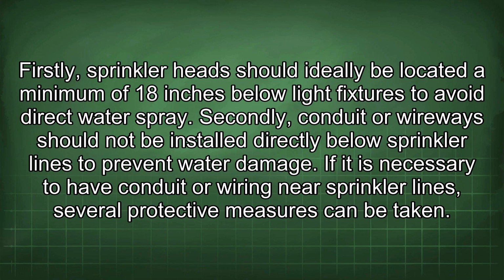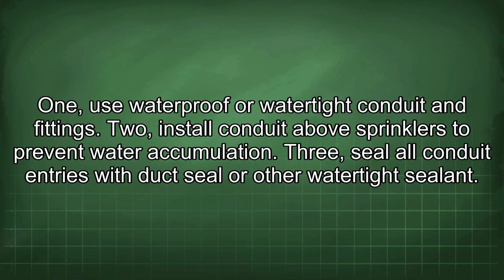If it is necessary to have conduit or wiring near sprinkler lines, several protective measures can be taken. 1. Use waterproof or watertight conduit and fittings. 2. Install conduit above sprinklers to prevent water accumulation. 3. Seal all conduit entries with duct seal or other watertight sealant.